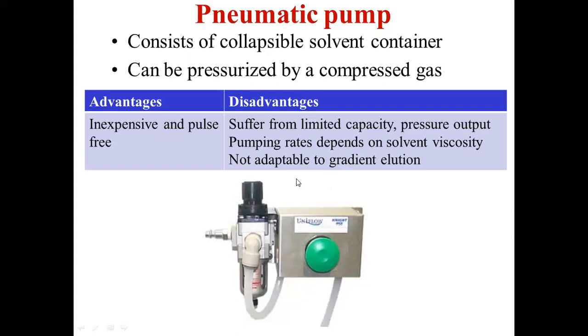And therefore, this is not adaptable for the gradient elution because a collapsible solvent container will be used and compressed gas is required. The gradient elution means a different variety of solvents are going to be used. Therefore, we cannot connect this pump to multiple solvent reservoirs. Multiple solvents are required in order to perform the elution by gradient technique. Therefore, this pump is not suitable for gradient elution.